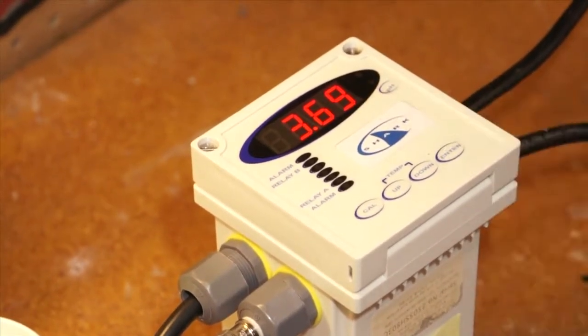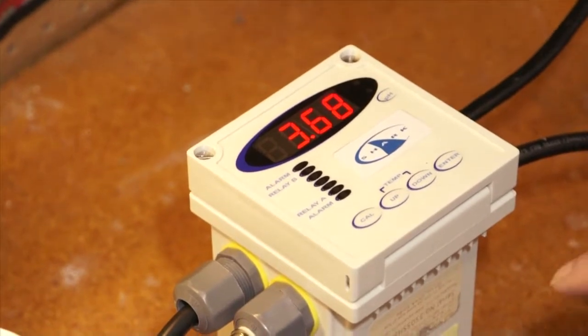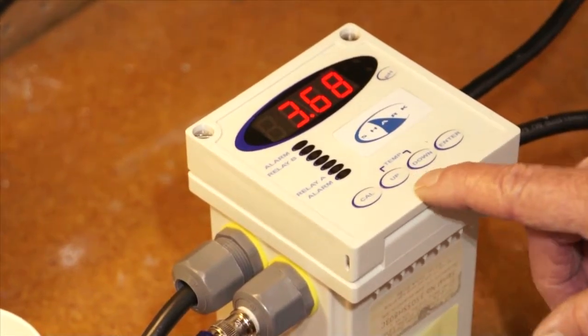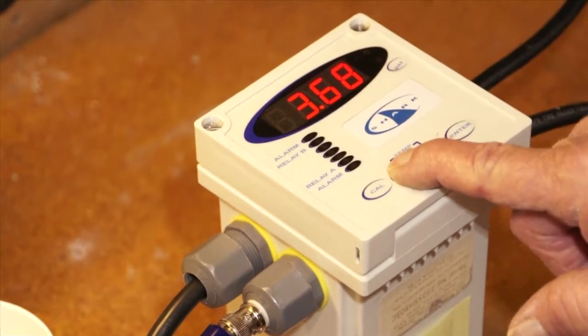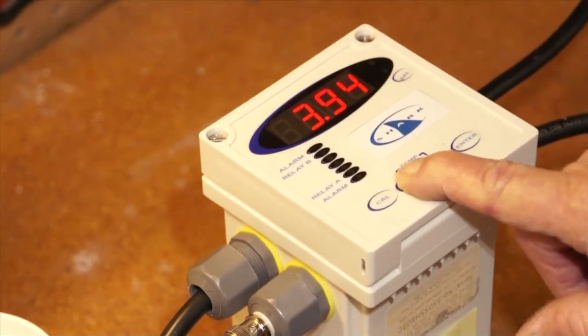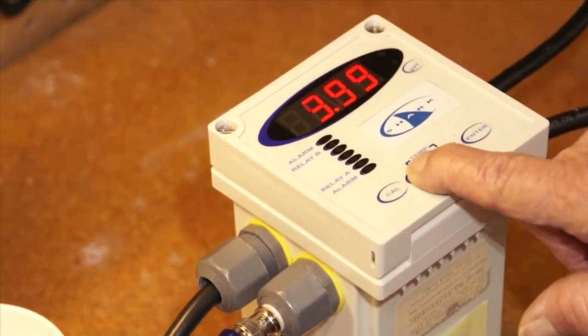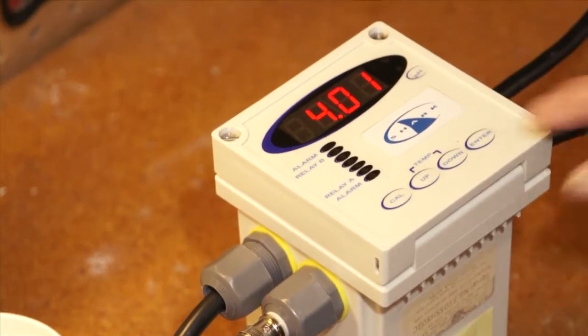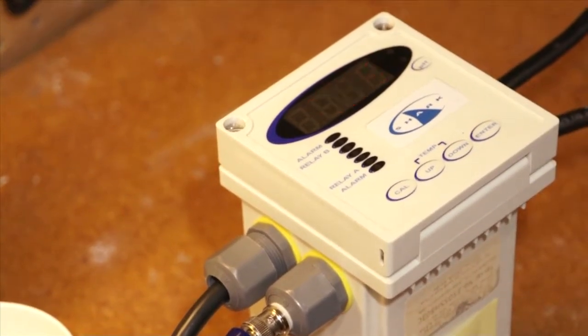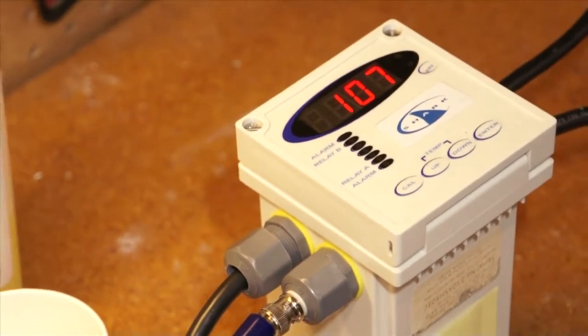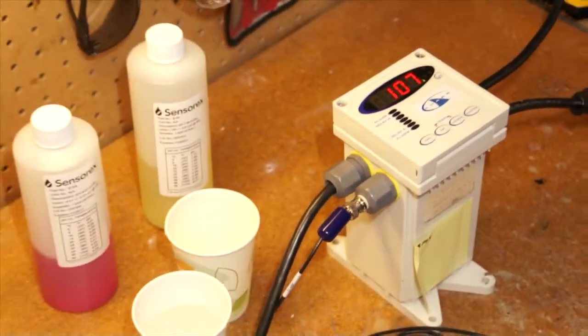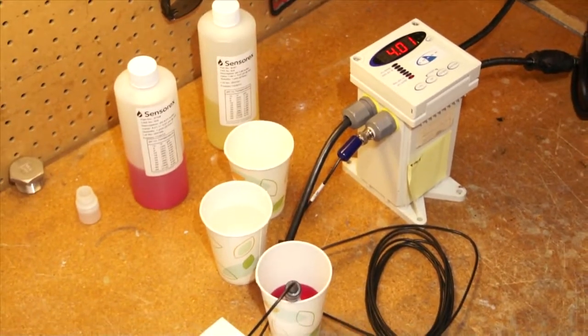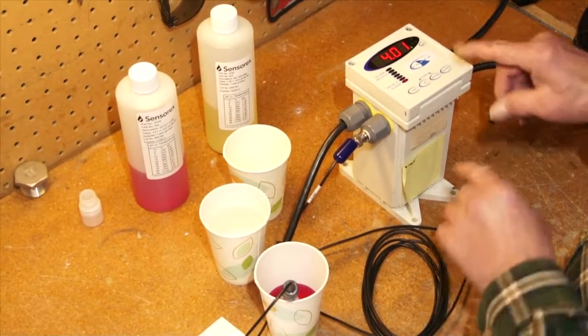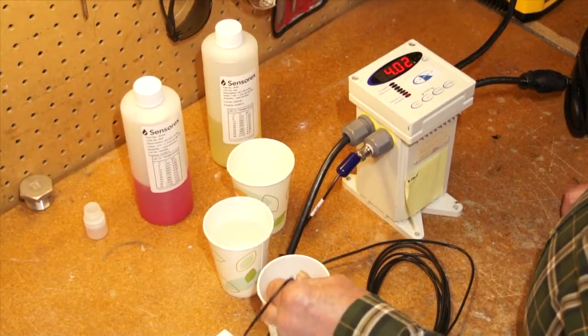Okay, that should read 4.01, it's 3.69, so we're going to adjust the controller to the actual pH of the buffer, 4.01. We will hit enter and enter again, and the EFF stands for efficiency. It's 107%. Very good, and it has reverted now to just run operation.